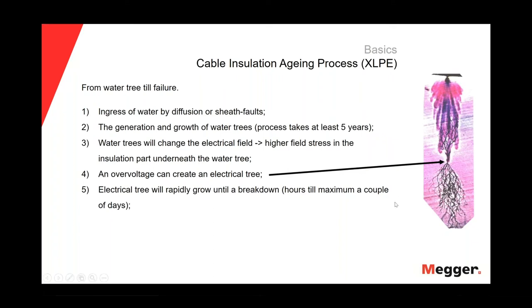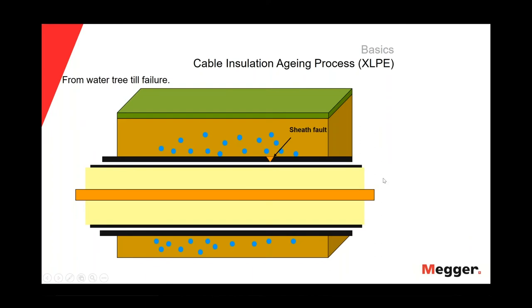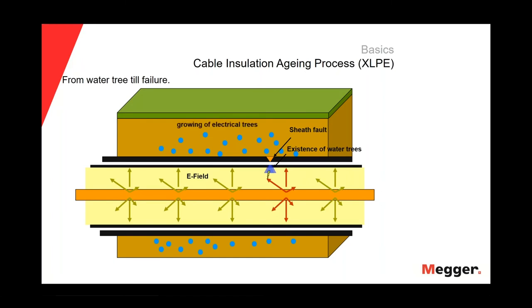To illustrate this process, we have this picture, and it all starts with a sheath fault in the cable. The water surrounding the cable will ingress in the insulation around my cable, and then I will have the existence of water trees, and the electrical field will convert that water tree into an electrical tree. And once we have an electrical tree, sooner or later we will have a breakdown of the cable.